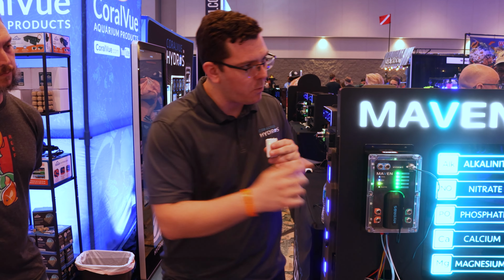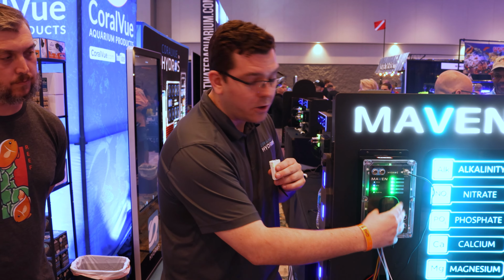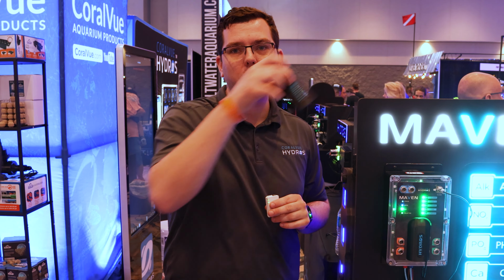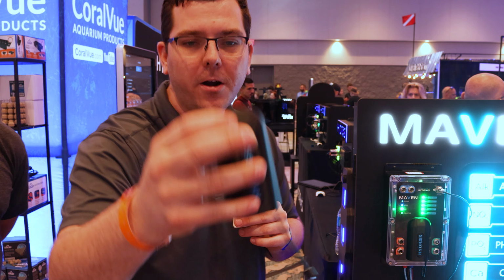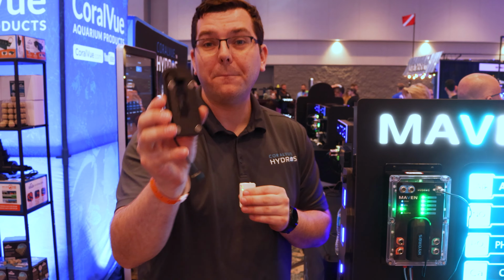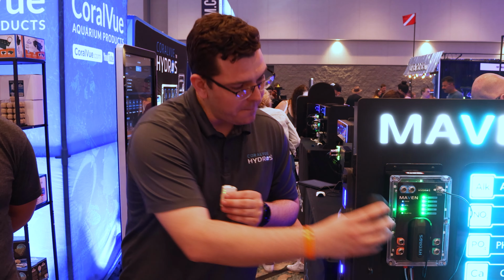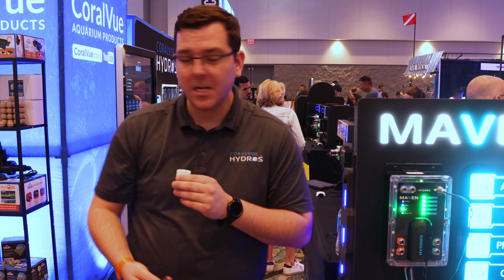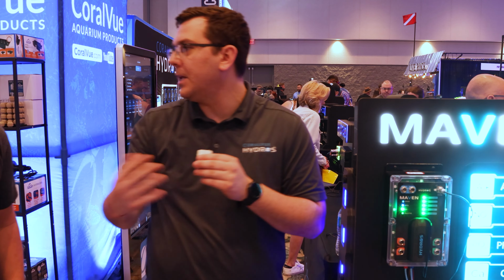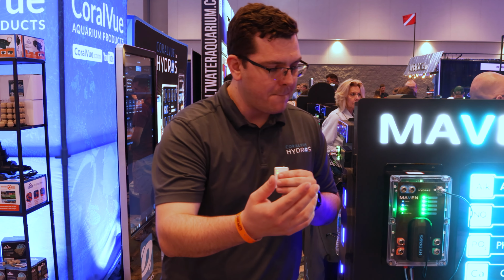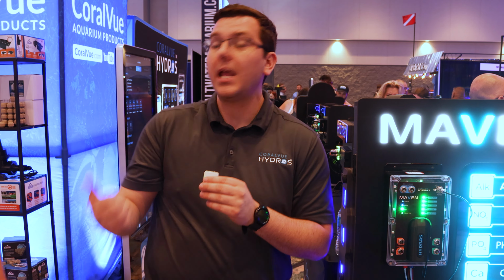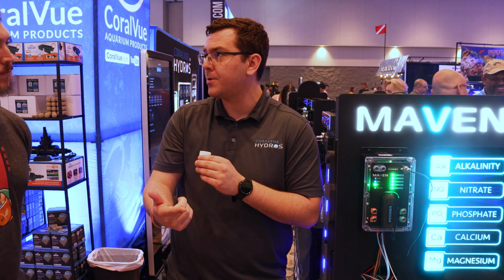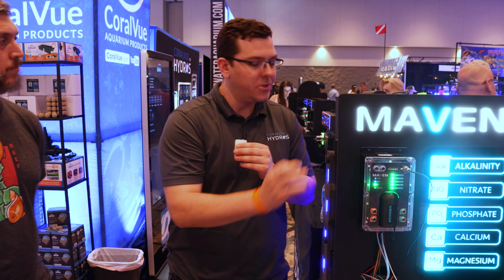Also, service and maintainability. So what you'll see right on the machine here is the cuvette holder and the cuvette blocker. And we can show the camera what that looks like. But right on the front of there, it's held down by 4 magnets with the cuvette on the back. So you can take this apart and maintain it, clean it, service it, and put it right back on the face of the machine. The entire thing is completely serviceable because we need it to be easy for users. The app is easy. We call it aquarium automation for everyone, and this can be no different. So that's the quick cleaning.